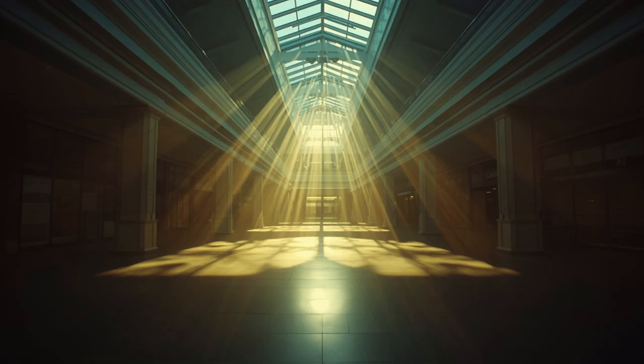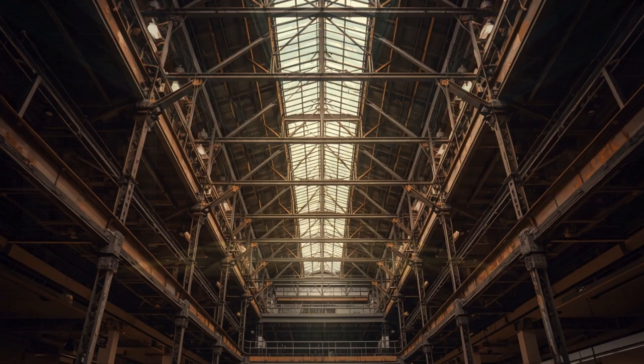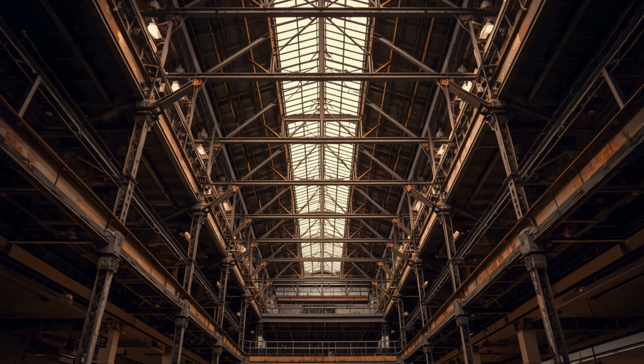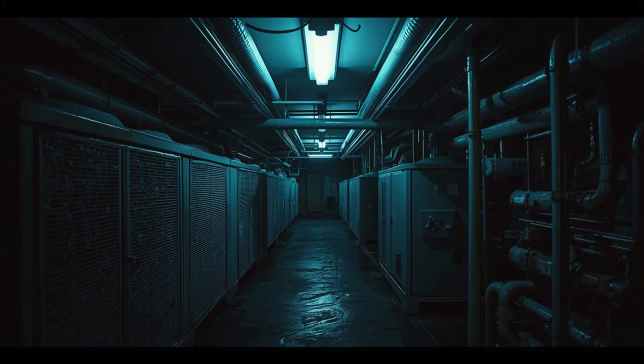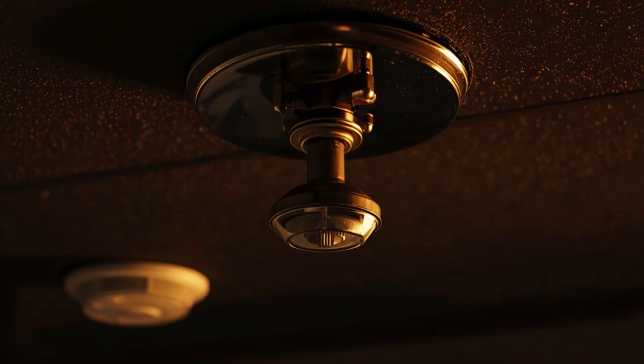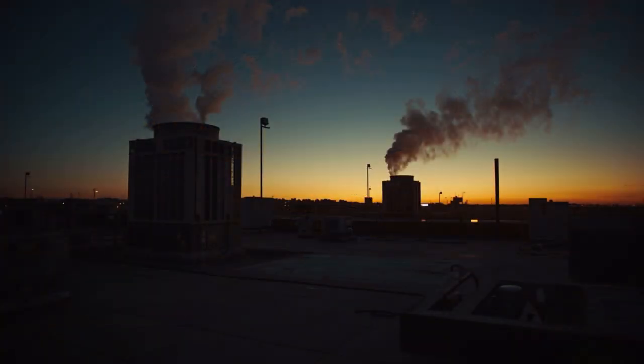The heart of the mall's cooling system was the chiller, a refrigeration machine that extracted heat from water, producing chilled water that could then be distributed through pipes throughout the building to cool the air. The chillers used in major regional malls of the 1980s were large, industrial-scale machines, centrifugal or absorption units capable of producing hundreds, or even thousands of tons of cooling capacity. A ton of cooling, in the terminology of the HVAC industry, represents the ability to remove 12,000 British thermal units of heat per hour, roughly the rate at which a ton of ice melts in 24 hours. A large regional mall might require 2,000 tons of cooling capacity, or more at peak summer conditions, with the atrium and its solar heat gain representing a significant fraction of that total.